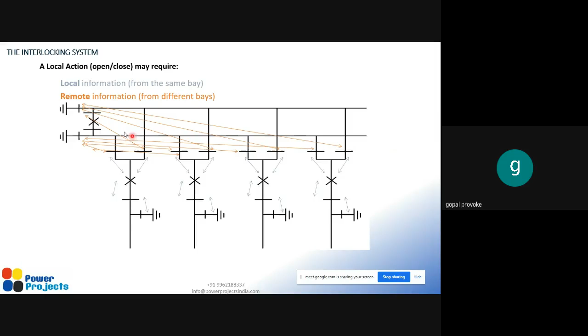For example, for the open status of the earth switch, we need a wiring, and for the closed status of the earth switch, we need a wiring, and likewise the open and closed status of the line isolator, the open and closed status of the breaker, and the open and closed status of the bus isolator. Similarly, for all the feeders in the substation, we need various signals, and these signals will be sent in the form of copper cable.